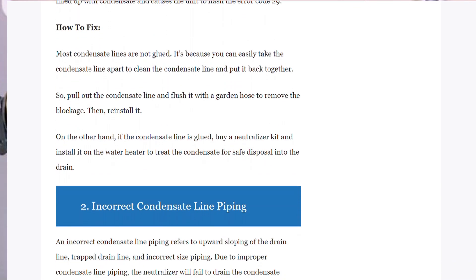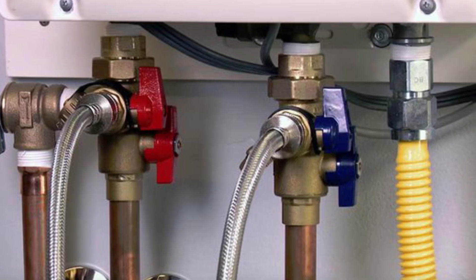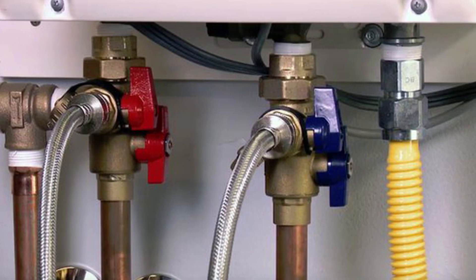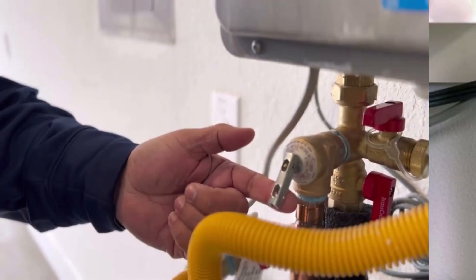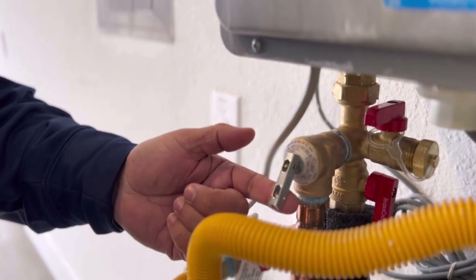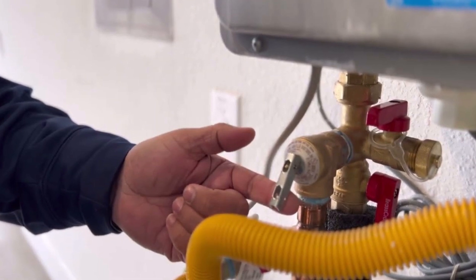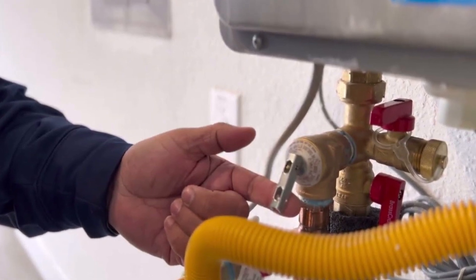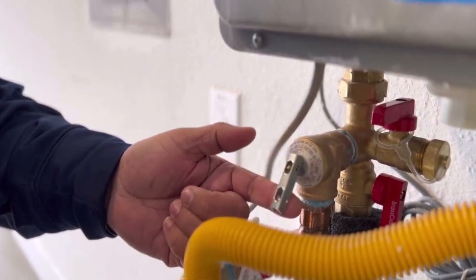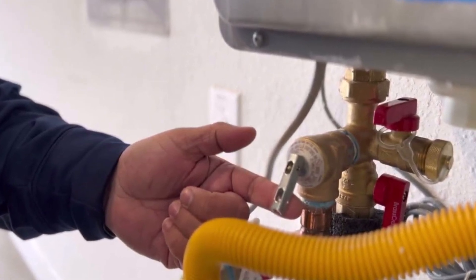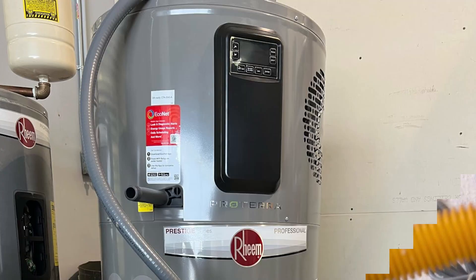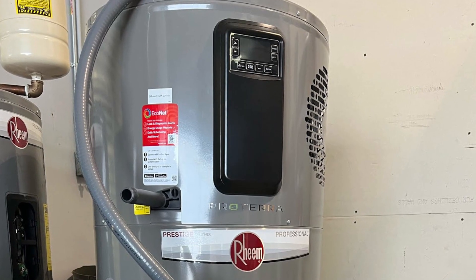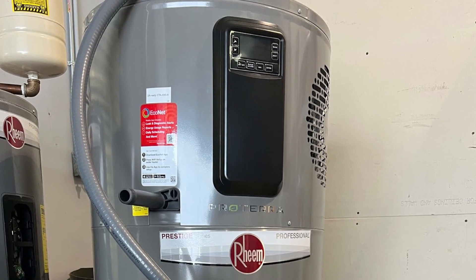Incorrect condensate line piping. The error may also occur due to incorrect size piping, a trapped drain line, or upward sloping of the drain line. These are mainly due to inappropriate installation of the pipes, or neglect and lack of adequate information.